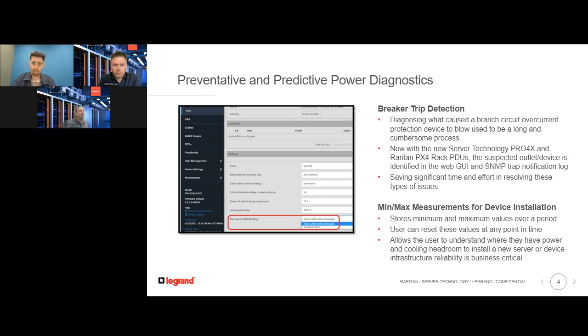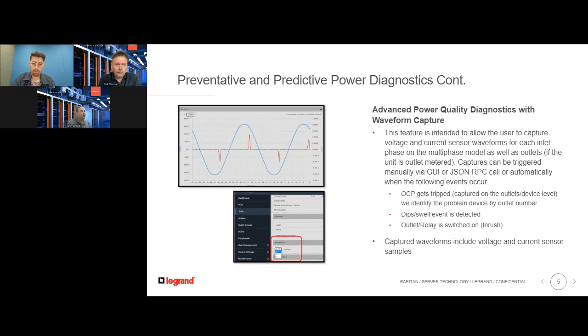So next, let's look at some of the other advanced diagnostics that we've got here. What's interesting about these is, again, it's unique. There's nobody that's doing this in industry. What's also unique is that we can automatically trigger these events based on certain things like the branch circuit breaker tripping. We can also look at it automatically for dips and swells. And then we can also look at it for current inrush, which I'll talk a little bit more about, which is still a problem today. And we'll talk about that in a little more detail.